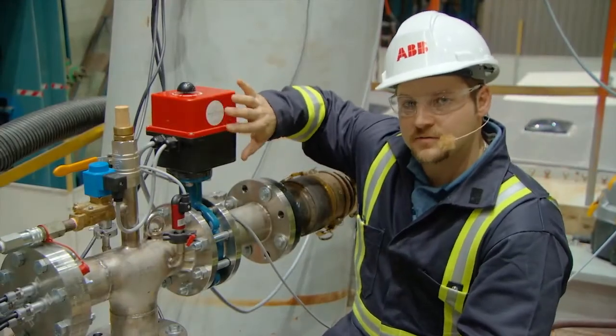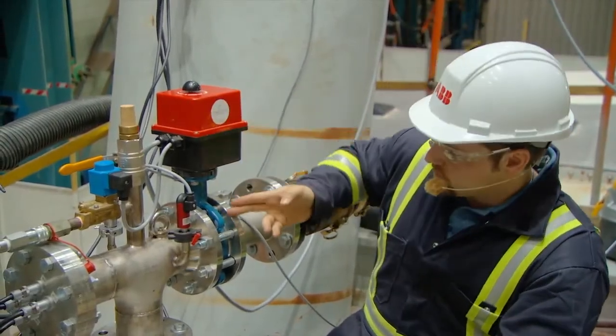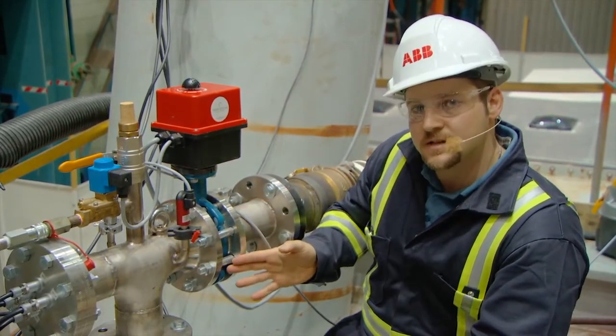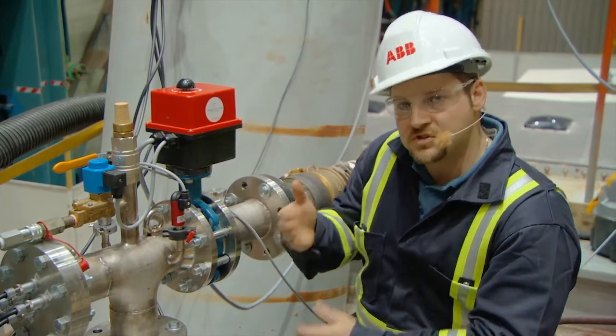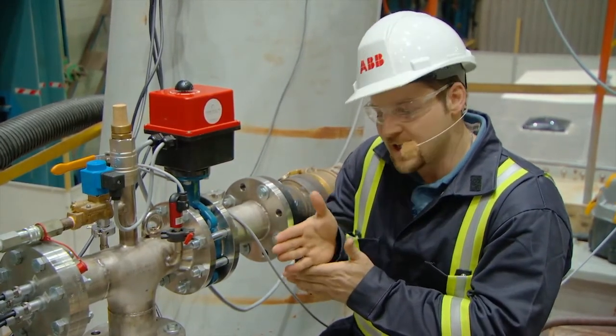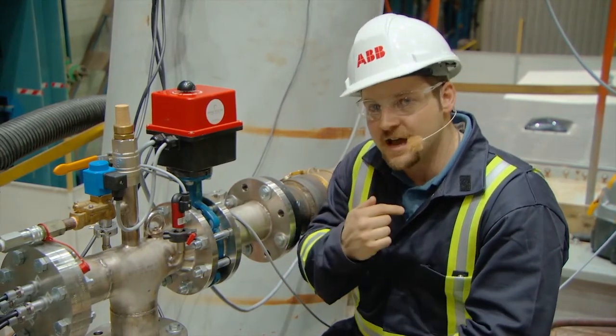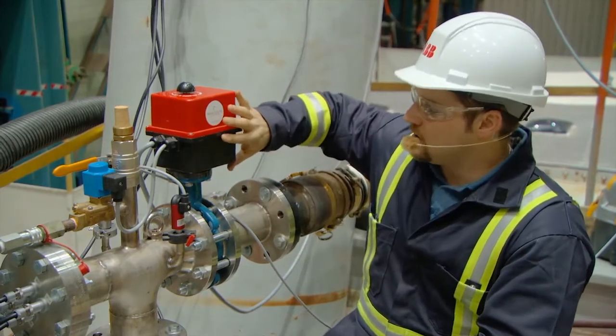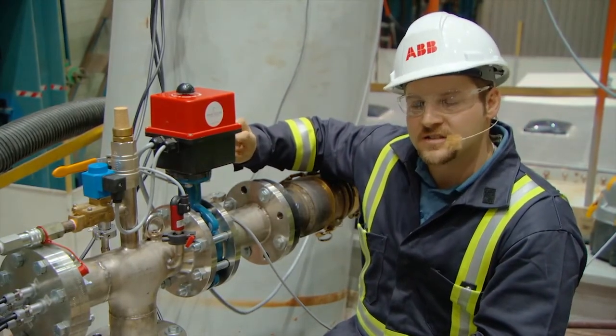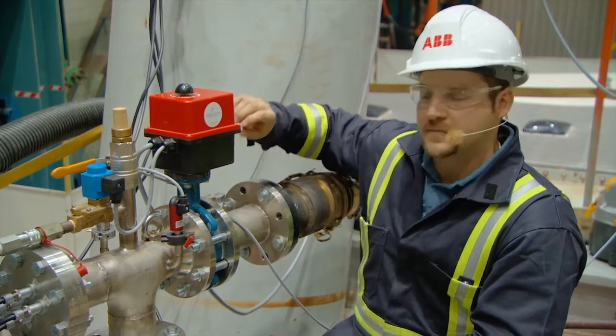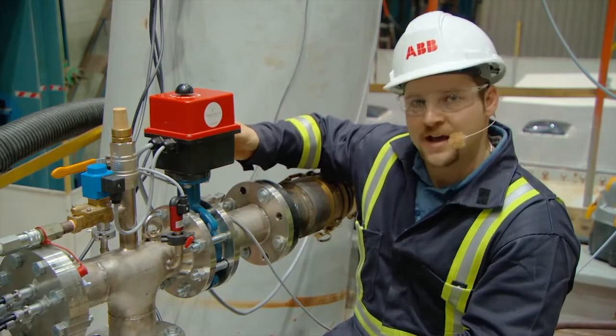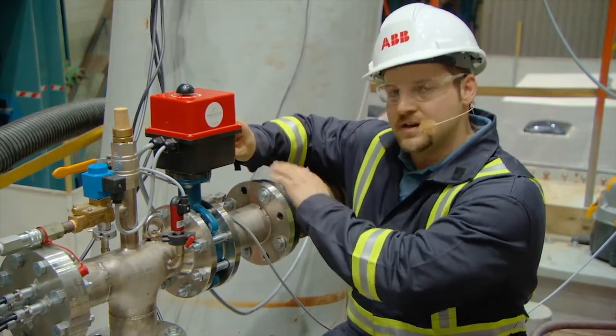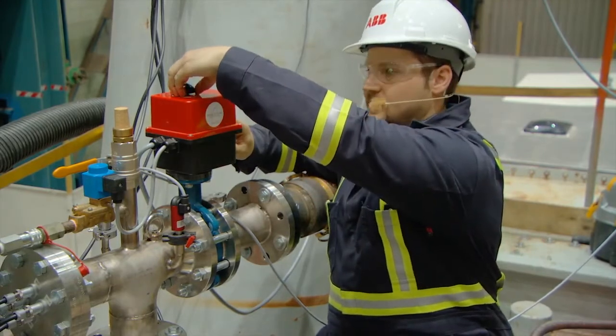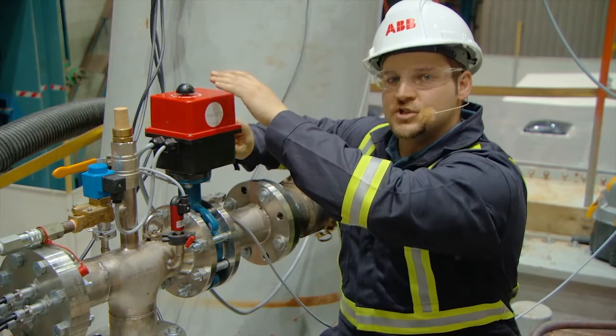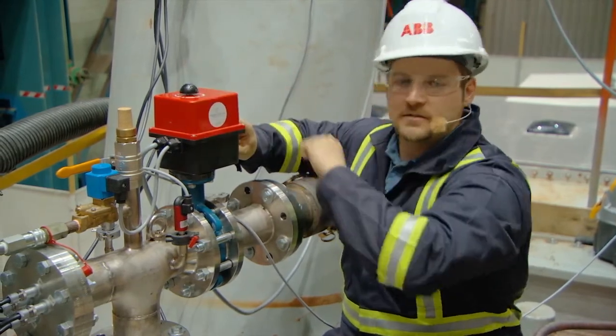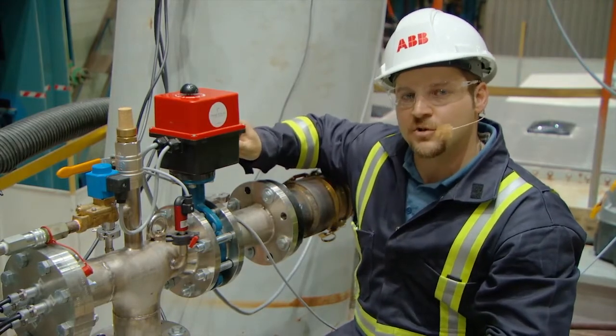Okay, this is the motor drive for the valve, for the positioning valve. This right here is the actual valve that's being positioned. It can be moved in any degrees from 0, which is fully closed, to 90 degrees, which is fully open, and any degree therein by using the HMI controls down on the computer. On this valve as well, there is also a manual override that you can use to set this valve manually in case of loss of power. There's a switch on the back that you turn to manual and hold it there. When you do this, on top of here, you take this indicator off and the shaft is actually keyed, so you can use an adjustable wrench to position the valve closed or open in case of any power outage or anything like that and you need to control the valve.